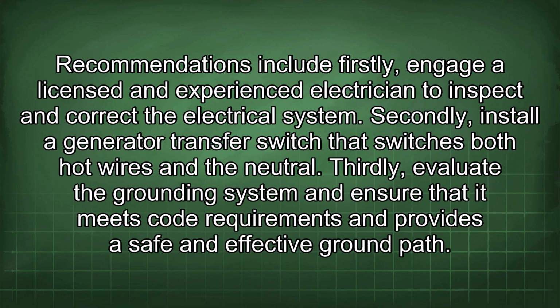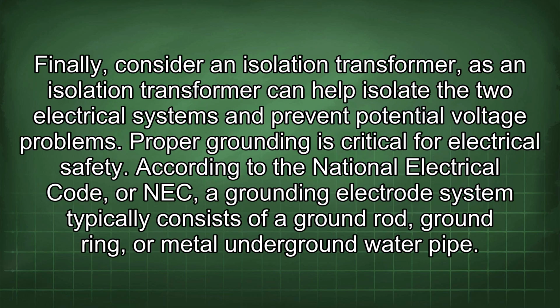Recommendations include: firstly, engage a licensed and experienced electrician to inspect and correct the electrical system. Secondly, install a generator transfer switch that switches both hot wires and the neutral. Thirdly, evaluate the grounding system and ensure that it meets code requirements and provides a safe and effective ground path. Finally, consider an isolation transformer, as an isolation transformer can help isolate the two electrical systems and prevent potential voltage problems. Proper grounding is critical for electrical safety.